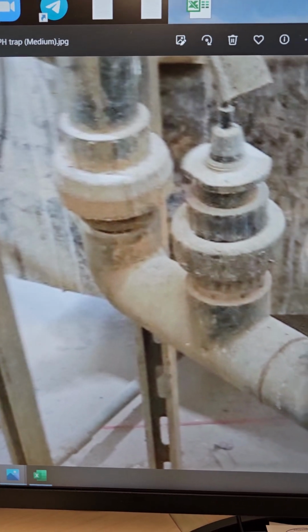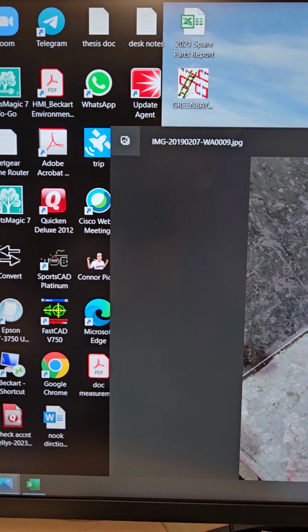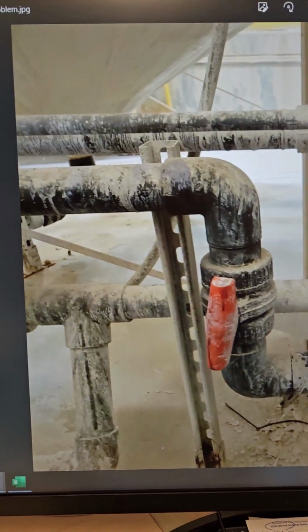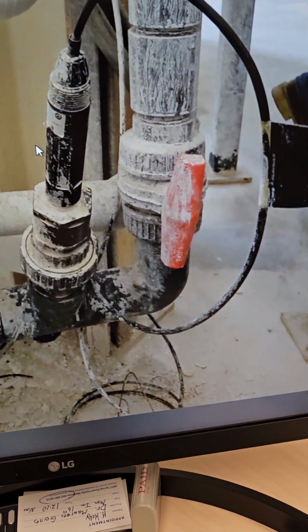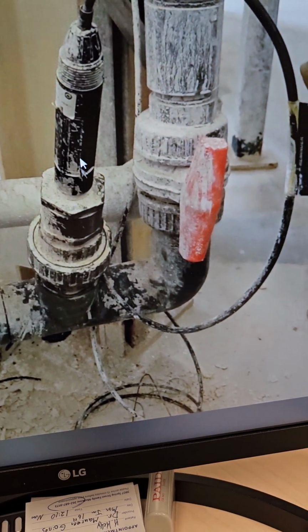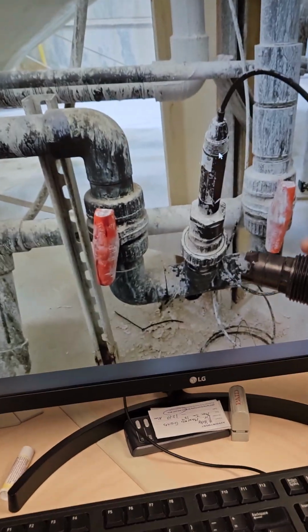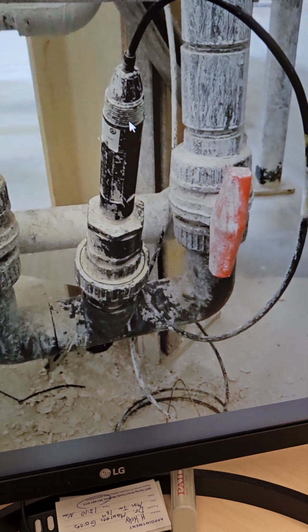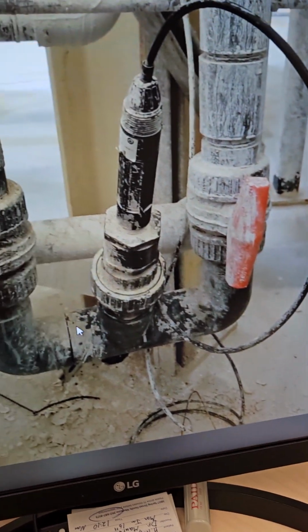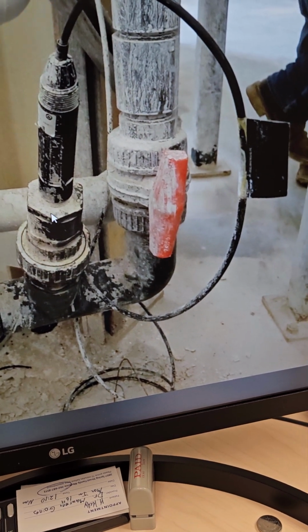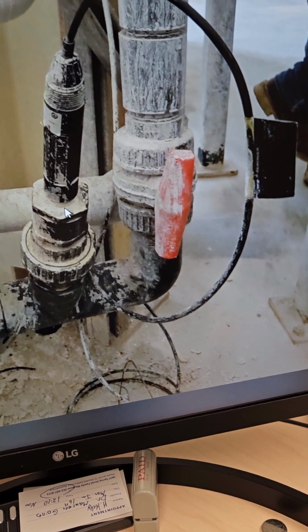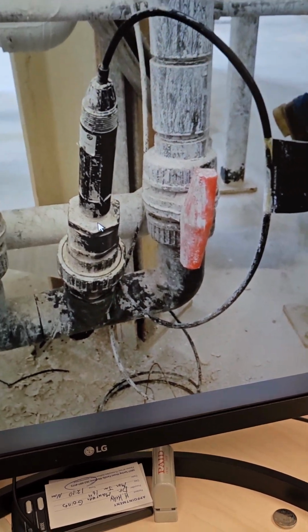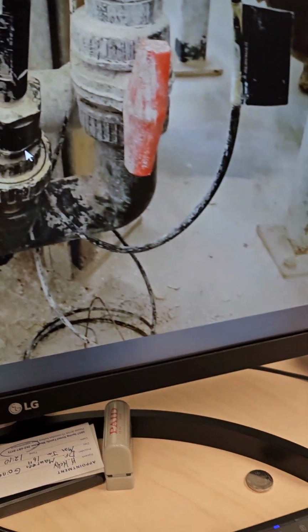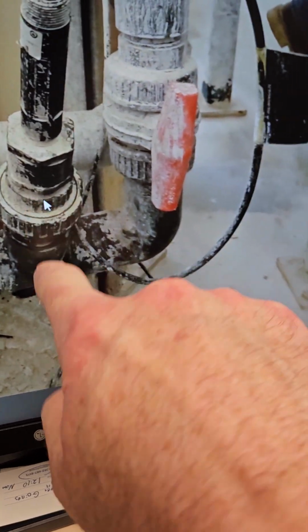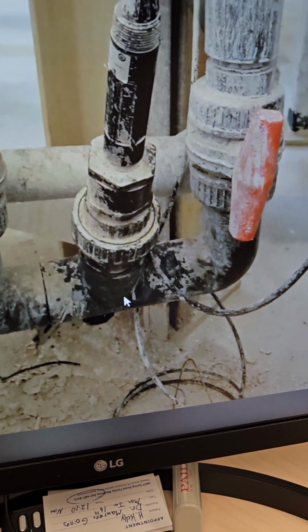Then some of the customers mistakenly put the adapter on the wrong side. If you get it on the wrong side, you have that adapter at the opposite end of the probe down here. Then the electrode is not going to be in the waste stream, and you're going to have problems. You're not going to get good readouts at all. The wastewater circulates through the bottom of the trap, and this will get air and sludge packed up in the top, and you'll get no good reading at all. So you need to take the threaded adapter off the end and move it to this end, and get rid of whatever adapter they've put in here, and they can go right into the threaded union. That'll get the pH probe down into the waste stream, so you get a proper reading.